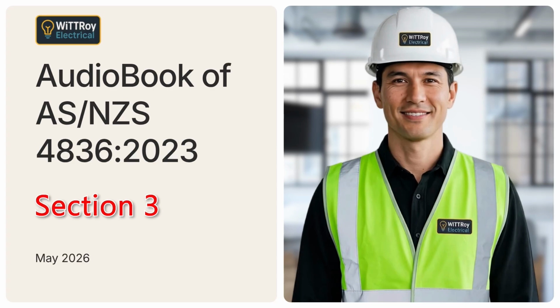Clause 3.1.2. Identification of electrical equipment and isolation points. Clause 3.1.2 explains that the equipment to be worked on must be positively identified. The points of isolation must also be positively identified. All energy sources must be identified, including non-electrical sources. This means the worker must know exactly what equipment is being worked on, exactly where it is supplied from, and exactly how it can be made safe.